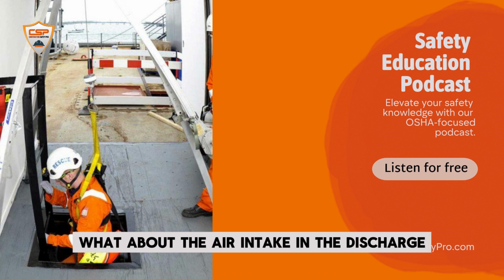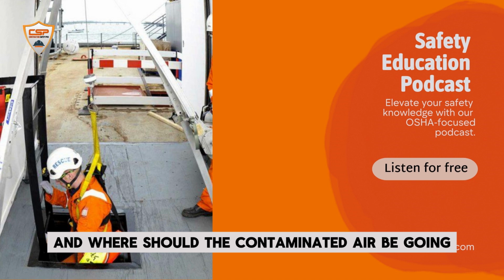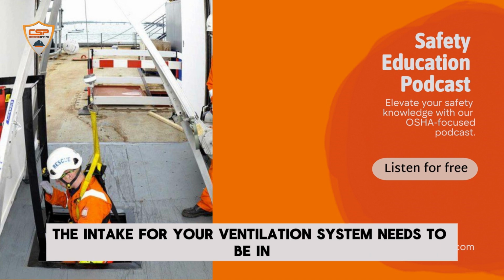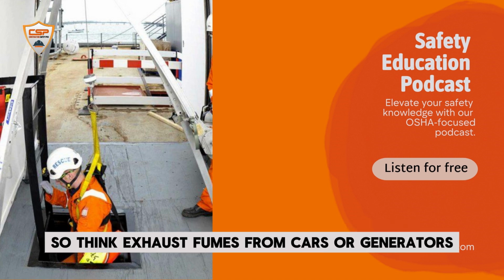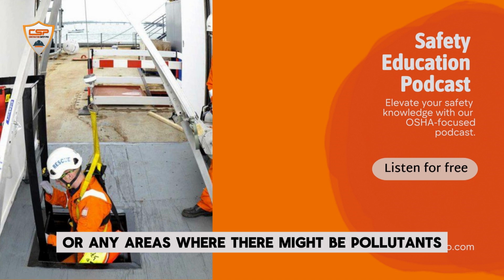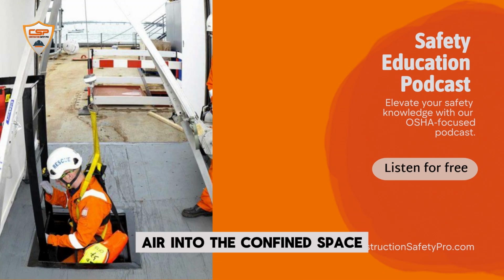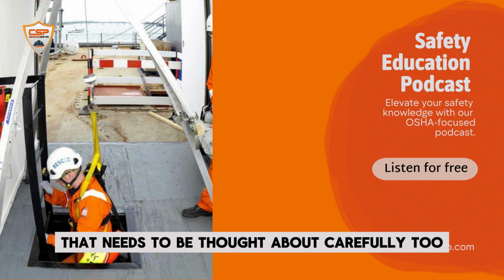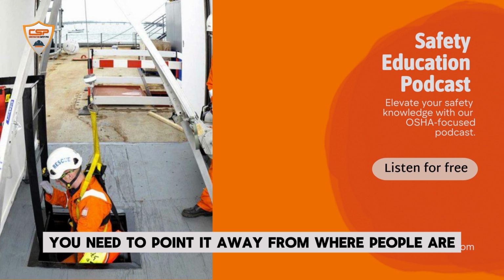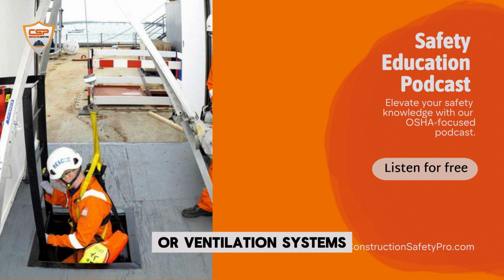What about the air intake and the discharge? Where should you be pulling in the fresh air, and where should the contaminated air be going? The intake for your ventilation system needs to be in clean, fresh air, well away from anything that could contaminate it. So, think exhaust fumes from cars or generators or any areas where there might be pollutants. The last thing you want to do is pump contaminated air into the confined space. And the discharge, where the bad air comes out, needs to be thought about carefully too. You need to point it away from where people are, walkways, and any air intakes for other buildings or ventilation systems.